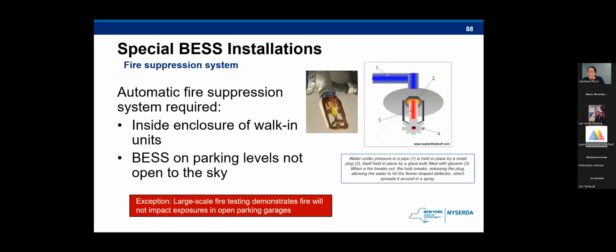So there's also a specific fire suppression requirement that both types of projects need to meet. And they have to have the automatic fire suppression system inside enclosures of walk-in units, but also battery energy storage systems on parking levels that are not open to the sky. So basically, as long as you're not on the top level, you need to have this requirement. But once again, it could be exempt if large-scale fire testing demonstrates that fire will not impact exposures in the open parking garage.